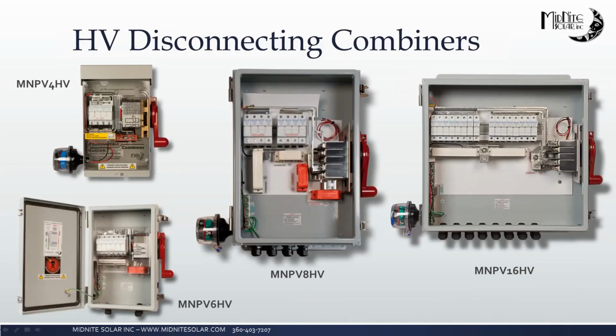Now we move into what we do call the high voltage disconnecting combiners. These are all birdhouse compatible. These all come with lightning suppression, fuses, fuse holders, strain reliefs, hole plugs, extra bus bars that you need, everything. They come in 4 string, 6 string, 8 string, 16 string. They come in a 3R style and a 4X style. You will notice that once you get to 8 string and above, they are what we call convertible. You'll notice in the picture here, the fuse holders are separated a little bit, and there's a couple negatives and a couple positive outputs.